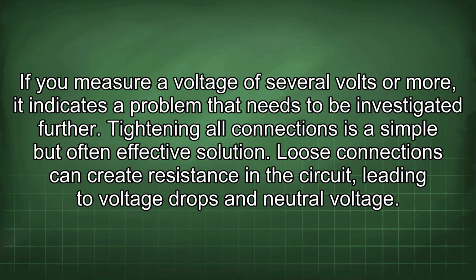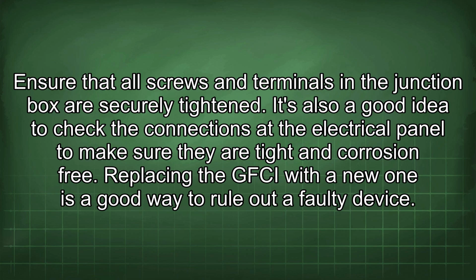Loose connections can create resistance in the circuit, leading to voltage drops and neutral voltage. Ensure that all screws and terminals in the junction box are securely tightened. It's also a good idea to check the connections at the electrical panel to make sure they are tight and corrosion-free.